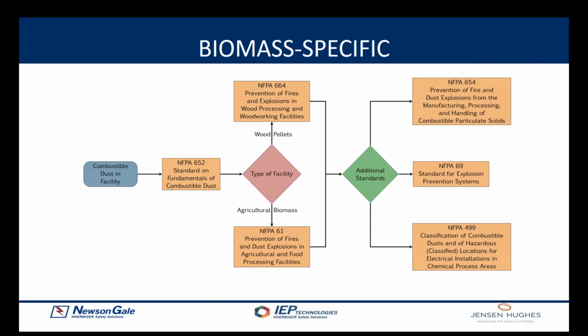This is a more specific graphic to biomass handling. Basically, whether it's wood pellets, you would use the occupancy-specific standard NFPA 664, and if it's an agricultural biomass, NFPA 61 is the governing standard. Once you've identified hazards and you intend to mitigate or prevent deflagration or explosion hazards, you would use more specific documents such as NFPA 69, 68, 499, or 654. 654 is a catch-all document that applies to dust-producing facilities where there are deflagration hazards, but they're not caught in either NFPA 664 or 484 or some of the other occupancy-specific standards.